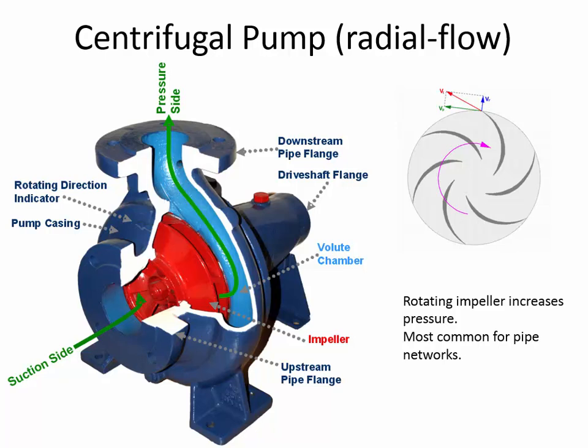By contrast, most commonly we're using radial flow pumps or centrifugal pumps. And these work by accelerating water and adding pressure instead of adding elevation. And so the way that it works is you have an impeller inside there that's spinning around very quickly, and it has different shaped blades depending on the configuration of the pump. Some pumps are designed to operate with a very high RPM, some slower RPMs, and the blade shape and thickness varies accordingly. But in each case, what's common to it is that the water enters in one direction on the suction side, and then it exits the pump in a different direction. So it's coming in and it's changing directions like a 90-degree angle.